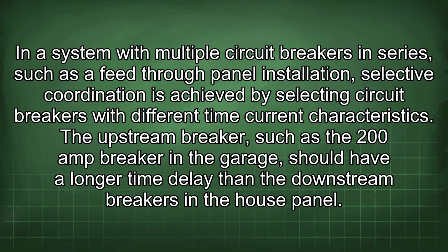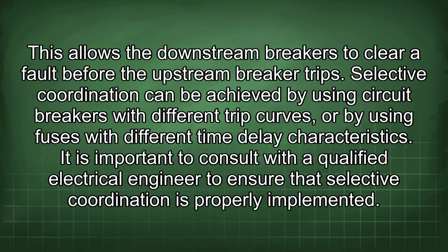The upstream breaker, such as the 200 amp breaker in the garage, should have a longer time delay than the downstream breakers in the house panel. This allows the downstream breakers to clear the fault before the upstream breaker trips. Selective coordination can be achieved by using circuit breakers with different trip curves or by using fuses with different time delay characteristics. It is important to consult with a qualified electrical engineer to ensure that selective coordination is properly implemented.